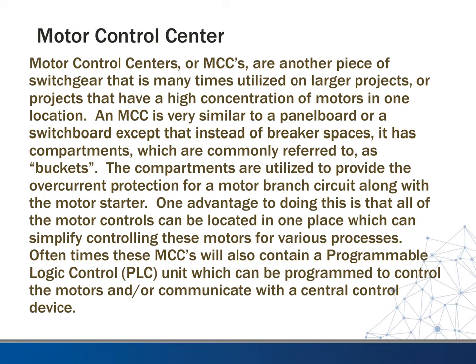So the compartments are utilized to provide the overcurrent protection for a motor branch circuit along with the motor starter. So one advantage to doing this is that all of the motor controls can be located in one place, which can simplify controlling these motors for various processes. Oftentimes, these MCCs will also contain a programmable logic or PLC unit, which can be programmed to control motors and/or communicate with a central control device.